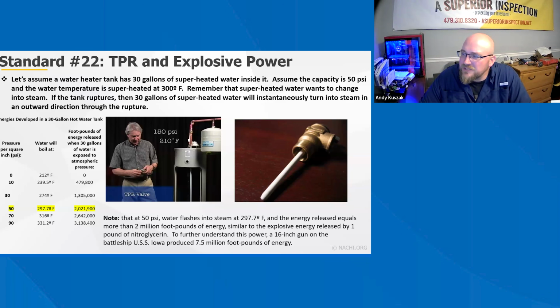There is a tremendous amount of energy released as the superheated water is exposed to atmospheric pressure, and it immediately turns into steam. Every cubic inch of water becomes a foot of steam. Below, to the side over there on the left, is a chart showing the explosive energy created in a 30-gallon hot water tank at various pressures and temperatures. This is why it is essential to avoid excessively high water temperature and pressure at the water heater.